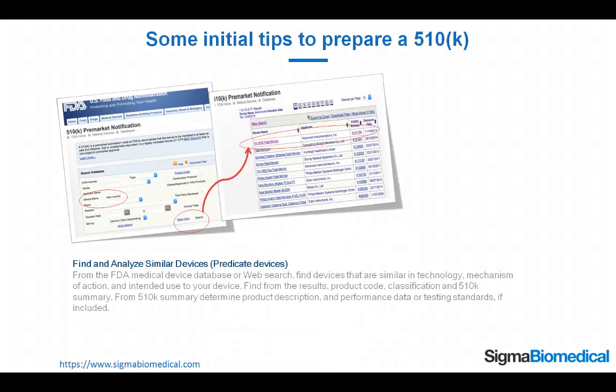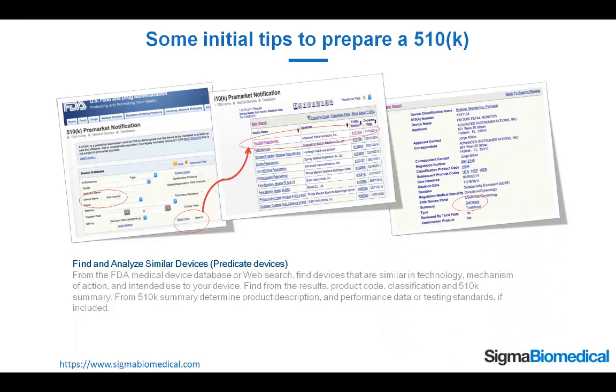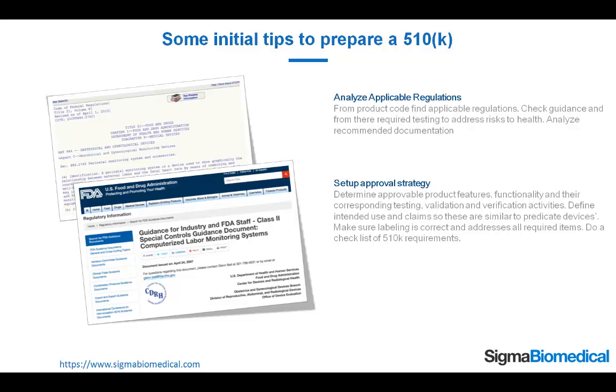Some initial tips to prepare a 510k. Find and analyze similar devices: from the FDA Medical Device Database or web search, find devices that are similar in technology, mechanism of action, and intended use to your device. Find the product code, classification, and 510k summary. From the 510k summary, determine product description and performance data or testing standards, if included. Analyze applicable regulations: from the product code, find applicable regulations, check guidance, and find required testing to address risks to health. Analyze the recommended documentation. Set up an approval strategy: determine approvable product features, functionality, and their corresponding testing, validation, and verification activities. Define intended use and claims so these are similar to predicate devices. Make sure the labeling is correct and addresses all required items. Do a checklist of 510k requirements.